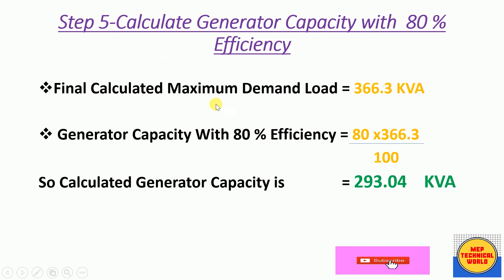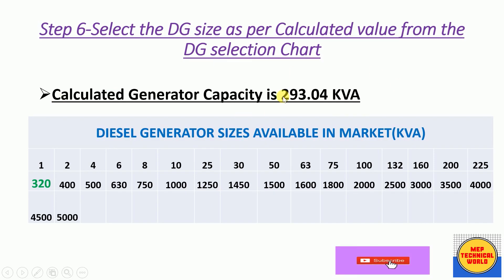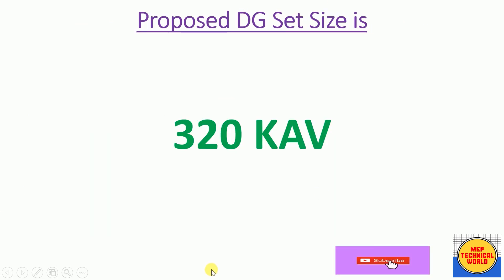In Step 6 we select the DG size from the DG selection chart based on the calculated generator capacity of 293.04 kVA. Looking at the DG selection chart showing sizes available in the market, the nearest available size above 293.04 kVA is 320 kVA. Therefore, our proposed DG size is 320 kVA.